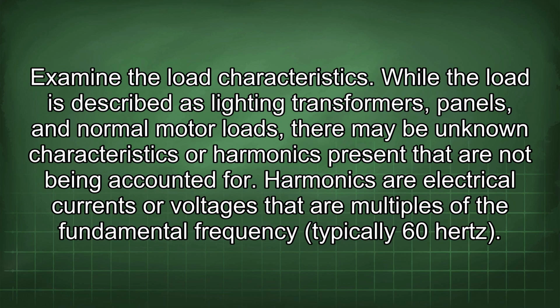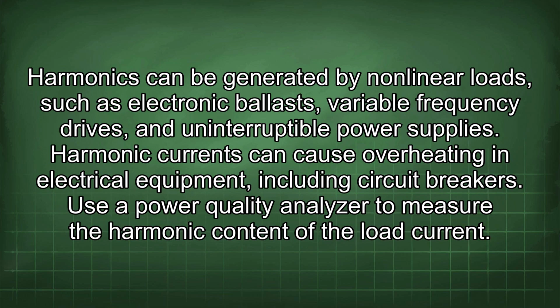Examine the load characteristics. While the load is described as lighting transformers, panels, and normal motor loads, there may be unknown characteristics or harmonics present that are not being accounted for. Harmonics are electrical currents or voltages that are multiples of the fundamental frequency, typically 60 Hz. Harmonics can be generated by nonlinear loads such as electronic ballasts, variable frequency drives, and uninterruptible power supplies.